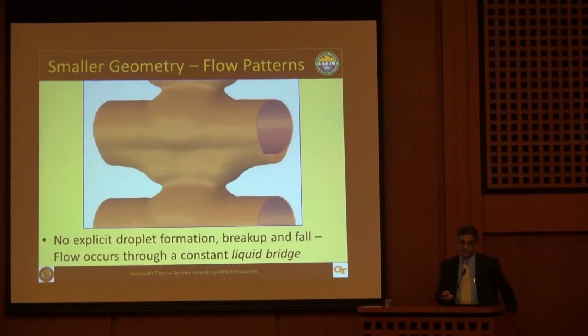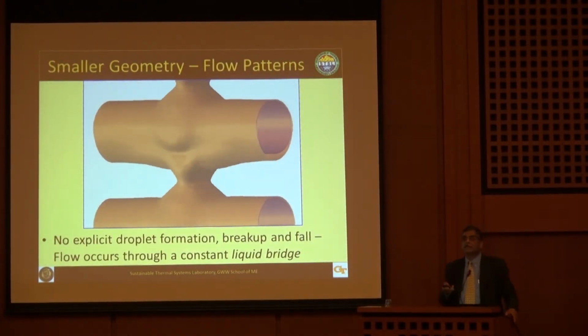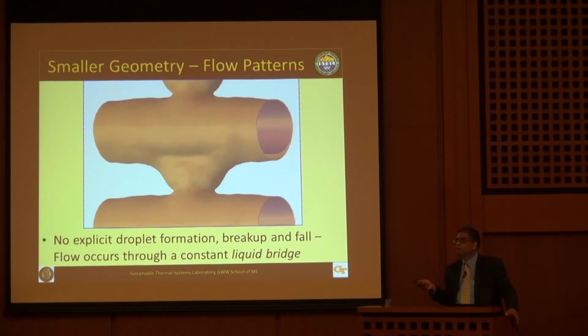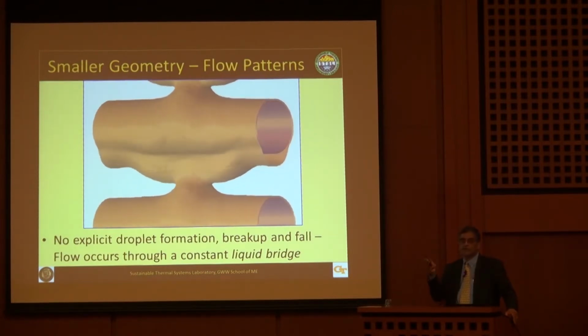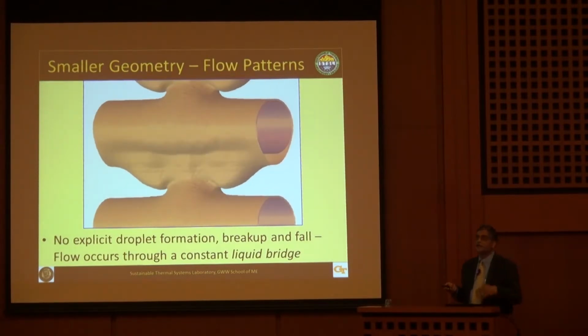This gives us insights into how you can design these kinds of tube banks. If you don't pay attention to that droplet formation and the optimal distribution of the tube bank spacing, you get this. This is not a good configuration because the film thicknesses are too high. This is a poor heat transfer mechanism. You're also not getting any droplets for additional absorption. So we can use our insights to design better systems.